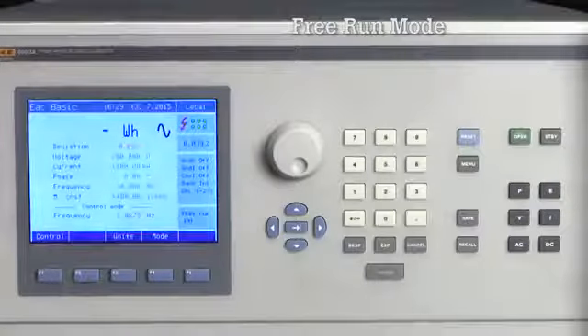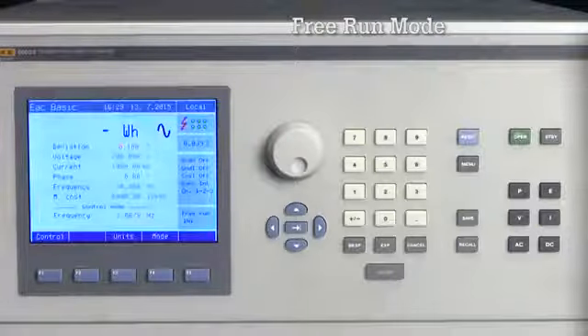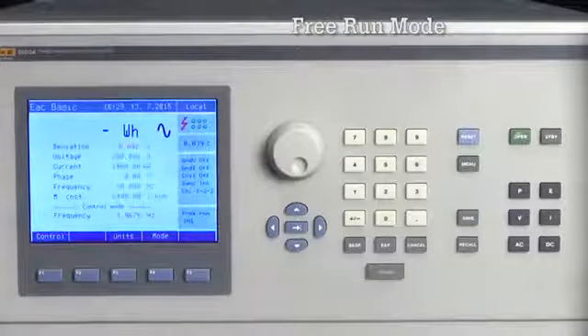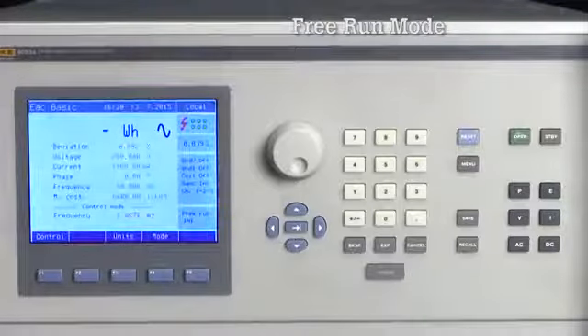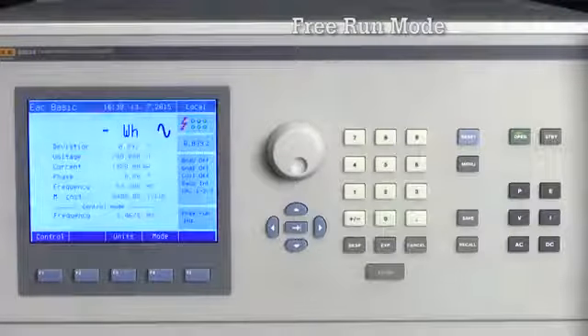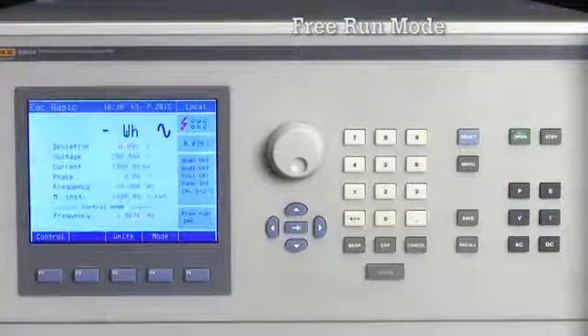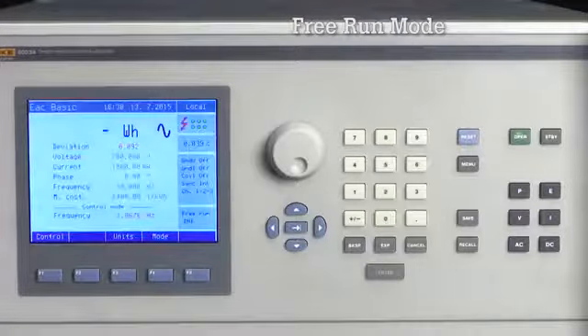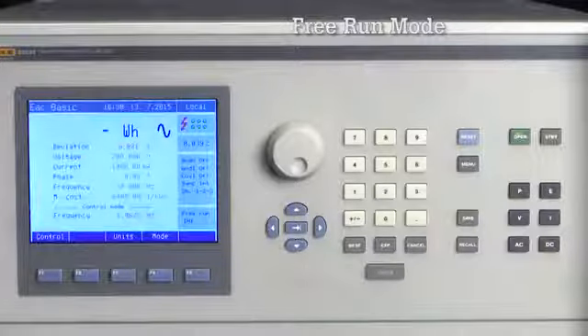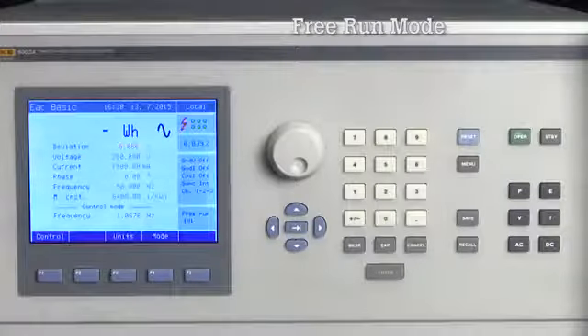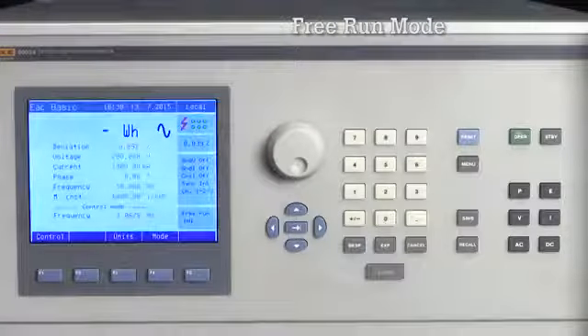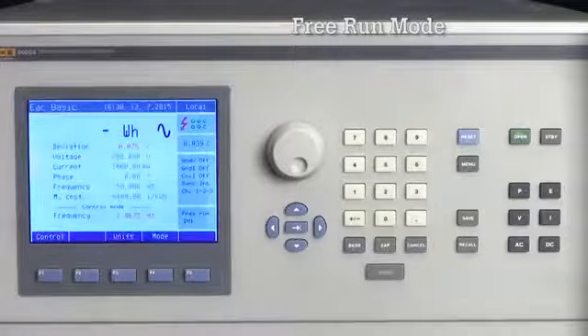The 6003 outputs 200 volts 1 amp into the UUT. In other words, it delivers 200 watts to the meter. The 6003A receives the pulses back from the meter and based on the meter constant expects an exact frequency of the pulses. The 6003A continuously shows the deviation between the measured frequency and expected frequency as a percentage. The meter we are testing is a 3-phase class 0.2 energy meter, and based on this measurement, the meter is well within that specification window.